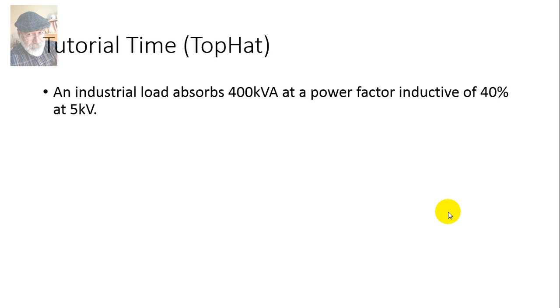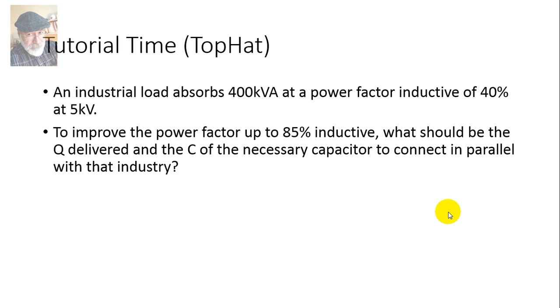It's absorbing that 400 kVA of apparent power at an inductive power factor of 40%, at a voltage of 5 kilovolts. To improve the power factor up to 85% inductive, what should be the Q delivered and what should be the capacitance of the capacitor we need to connect in parallel with that industry? We want to go from 40% to 85%.